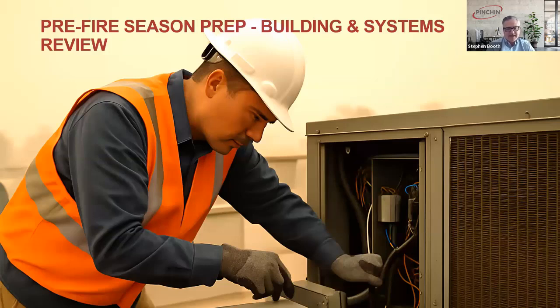Look at your HVAC systems' compatibility. So can the systems you have support MERV 13 or higher filters? Can you set those systems on a recirculation mode? Is that configurable via your BMS, or do you have to send someone up to the unit to do that manually? Are the economizers controllable? The last thing you want is an economizer system that's designed to bring in free cooling in the spring and brings in lots of outdoor air, opening up automatically to help control the temperature during an early season smoke event, right? We want to make sure that doesn't happen and those systems are shut off during those periods. And then, just confirm the maintenance status.